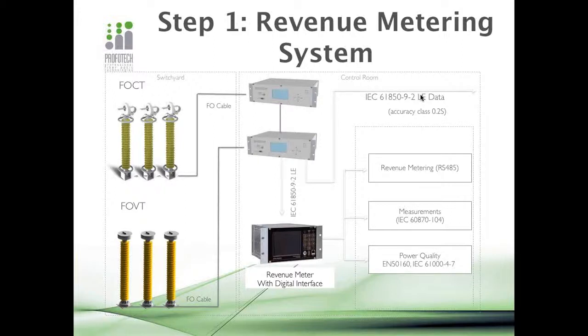You can see on the slide that we have some groups of fiber optic CTs and fiber optic VTs. They interface with the electronic modules installed in the control room of the substation. And we have only fiber optic cable between them, no copper wires. And then these electronic modules organize the so-called process bus, the IEC 61850-9-2 LE interface, that can be used both with the revenue meters, with protection devices, and so on and so forth.